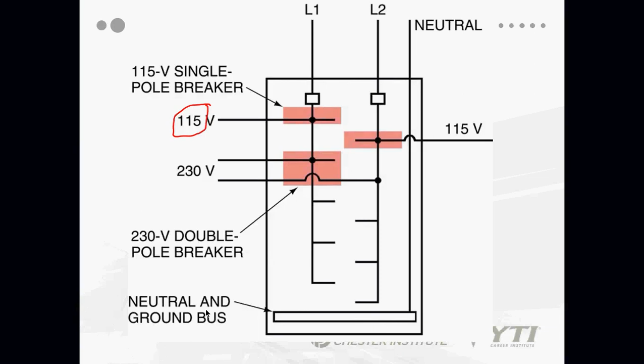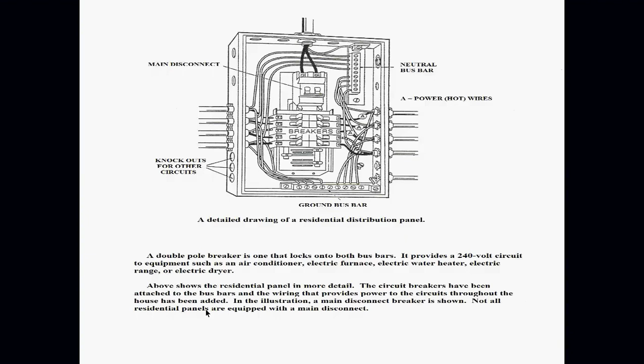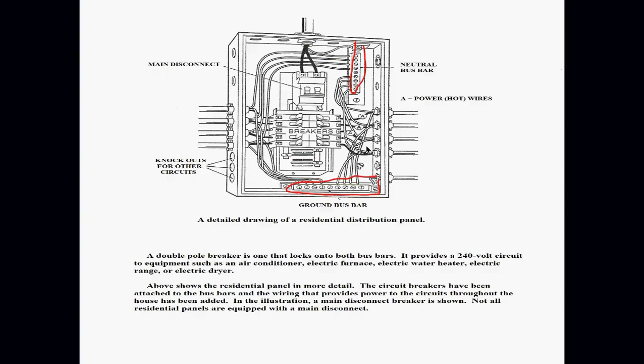Double pole breakers go across both L1 and L2. In a perfect world, our loads are balanced between the L1 and the L2. We don't put all the load on one or the other. Breaker panels are supposed to be wired neatly. You'll have a neutral bus bar and a grounding bar. They are eventually bonded together. All your neutrals come into one place, so you have a whole bar with white wires, and a whole bar with either green or bare copper wires. They are bonded together, eventually.